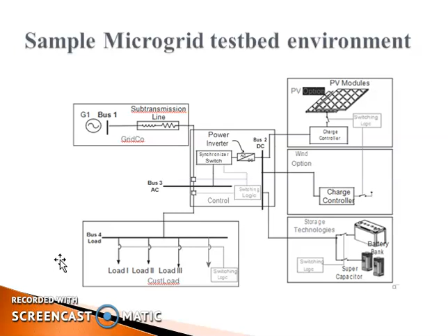Then let us glance at what a microgrid test bed is. A microgrid test bed is a collection of HIL devices from Typhoon HIL with integrated distributed energy resources controllers, protection relays, and microgrid controllers. HIL means hardware in the loop devices, where the hardware is also included as a part of the system. It becomes very portable when the model itself is processing and it is loaded into a particular system. The main purpose of the microgrid test bed is to comprehensively test the controller's hardware, its firmware, software, as well as all the communication aspects. Are all operating perfectly or not? The condition of all these devices is very important.